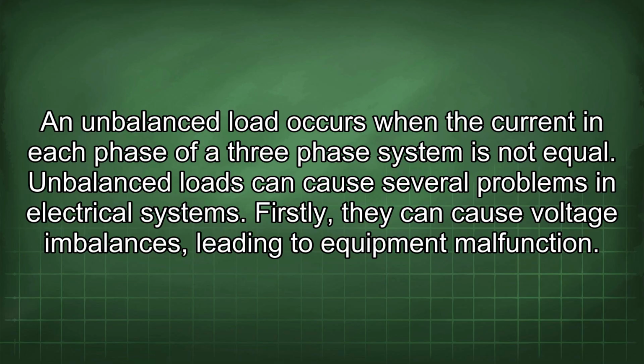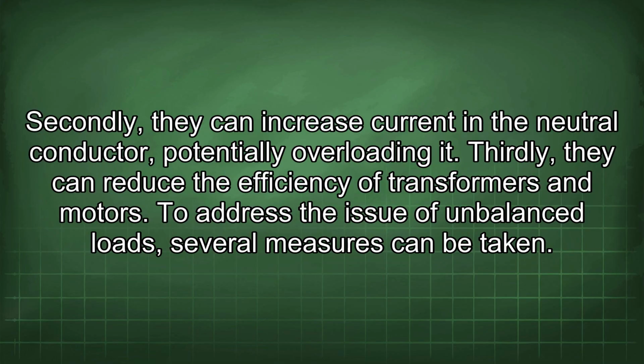Unbalanced loads can cause several problems in electrical systems. Firstly, they can cause voltage imbalances leading to equipment malfunction. Secondly, they can increase current in the neutral conductor, potentially overloading it. Thirdly, they can reduce the efficiency of transformers and motors.